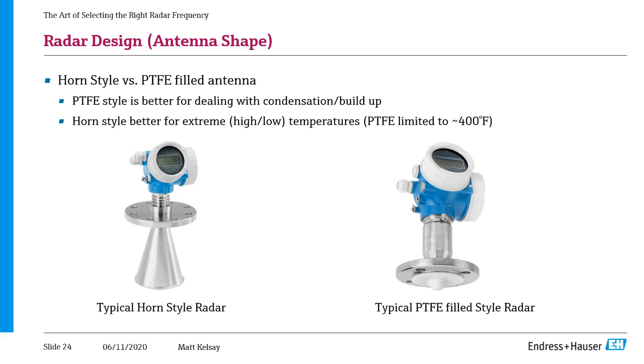So this point, in terms of the antenna shape and the design, isn't necessarily directly related to frequency, but it is an important conversation nonetheless, so I wanted to cover it for just a second. There are really two main types of radar antennas. Those that have the big metal horns, like on the left, that protrude down from the process connection, and those that are more of a flush mount design. So this flush mount PTFE Teflon style design is better with handling condensation and buildup.